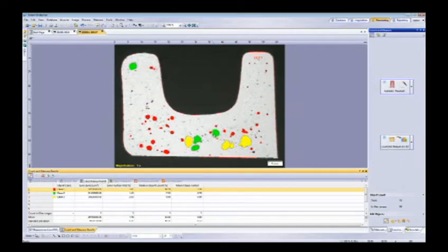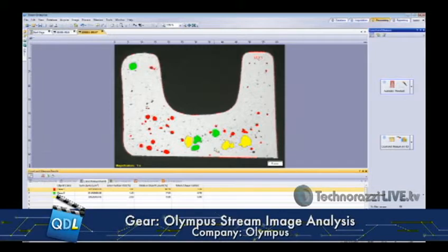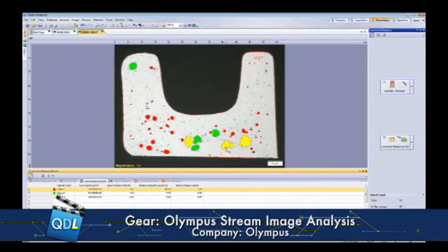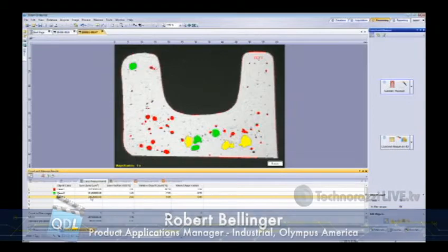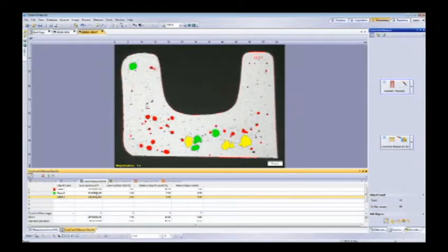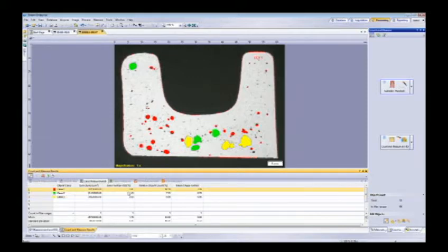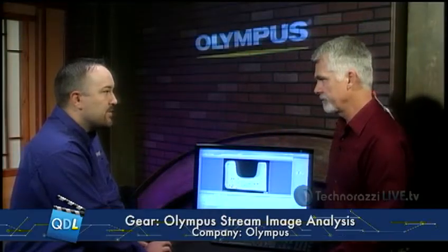So with automatic, you select it, hit Count and Measure on a region of interest, and the software does the rest — it identifies, sizes, and classifies all the particles or voids in the sample. I see three different colors on here. Three different colors are determined by the class. We separate those classes by their area — large, medium, and small size class. The red ones are the small, green is medium, and yellow is larger. This gives us our total area in micrometer squared per class, the area fraction, and the relative object count within each class.